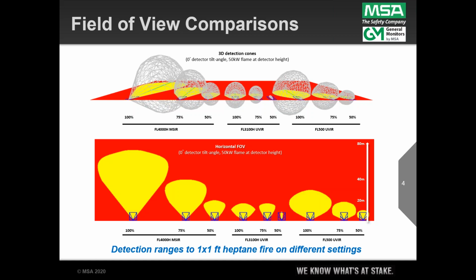50% represents the lowest sensitivity. So this is a comparison on the left of the multi-spectrum IR to that 1 by 1 heptane fire. On the far right is the model FL500 UVIR detector range to the same size fire. And you can see, sure enough, the MSIR has a much longer range. In the middle is our previous generation UVIR detector, called the FL3100H. With the FL500 coming out roughly a year and a half or two years ago, you can see how it leapfrogged the FL3100H in terms of its range and also its spread.